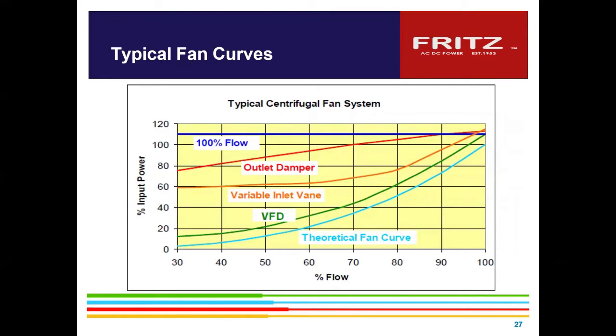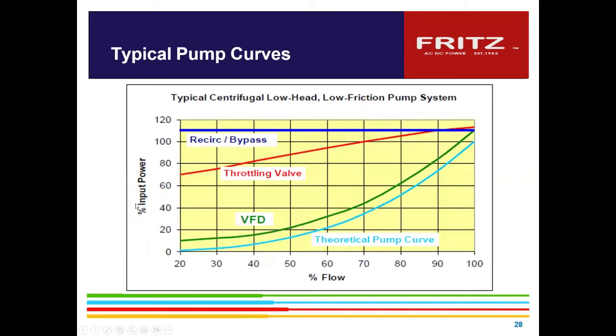So this is the typical difference at 100% flow rate with outlet dampers; you'll see that this is where the curve goes here. And then when you put the VFD in, you can see this differential in power here, and it becomes quite dramatic in power, and that's both in fans and pumps. Again, this is a little bit more on the pump curve.